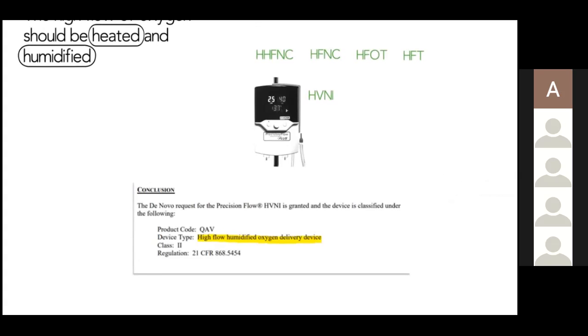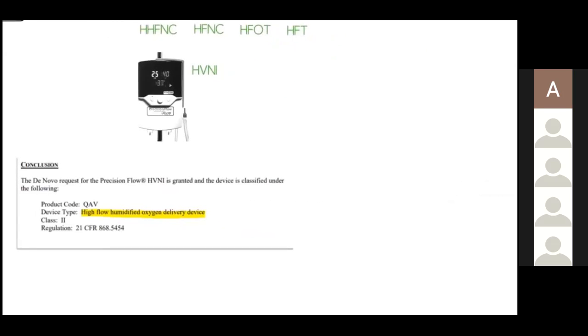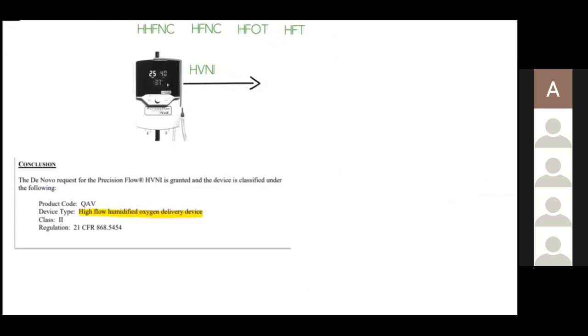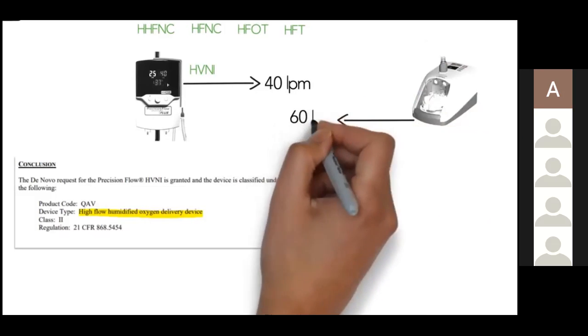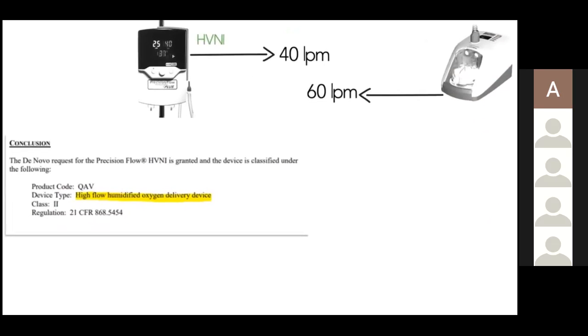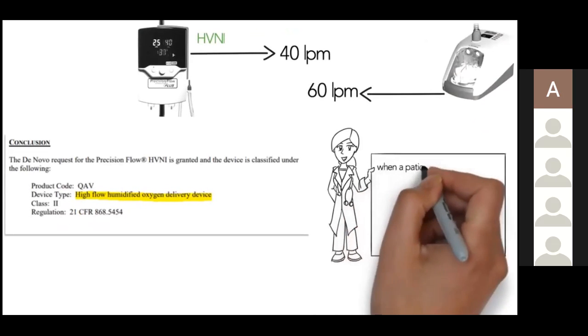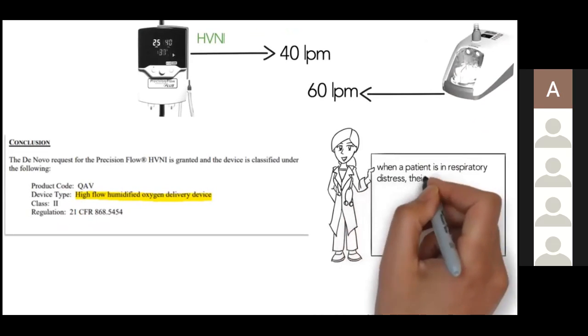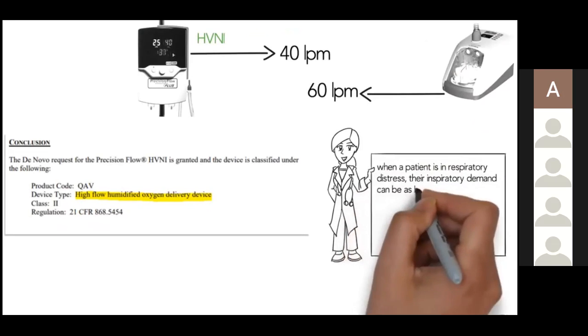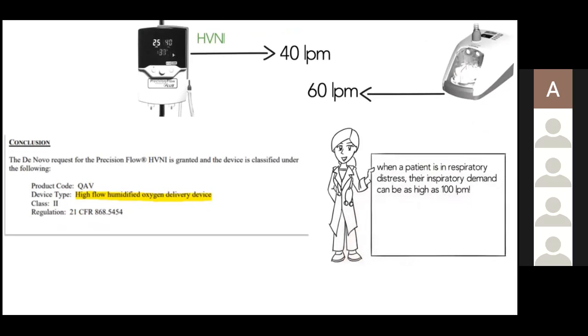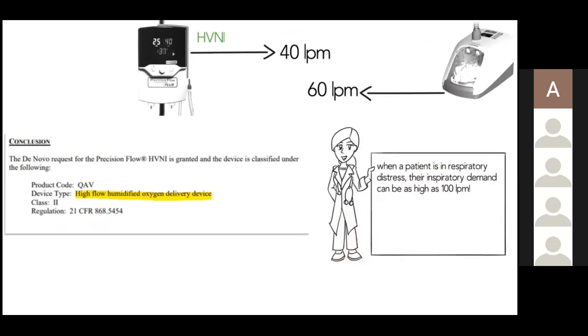Now, like other high-flow devices, they deliver a high flow of oxygen and it is heated and humidified to help meet patient comfort and tolerance. And some devices, like Vapotherm's Precision Flow, go up to 40 liters per minute. Others, like the F&P Airvo 2, go up to 60 liters of flow, while still others can go even higher. Because at the end of the day, we're just trying to meet the inspiratory flow of a patient, and when that patient is in respiratory distress, that inspiratory demand can be as high as 100 liters per minute.